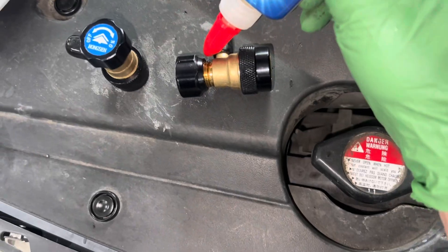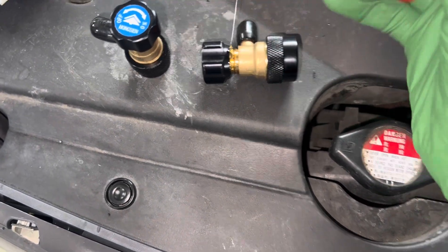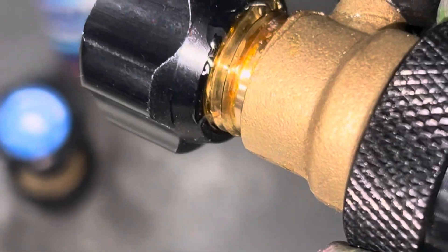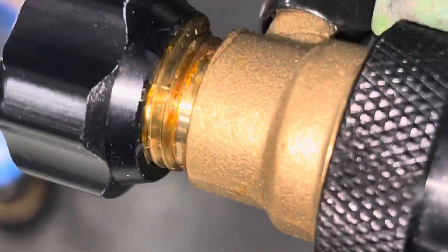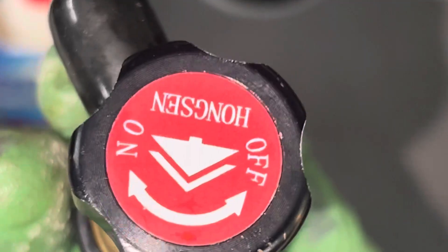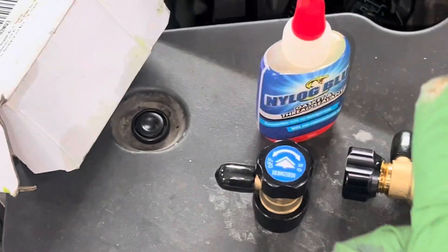I want to go 360 degrees — you see how I did right there, I went on the threads right there. If that goes 360 degrees all the way around, vacuum cannot be pulled up through the center shaft or up through there under that sticker. Those are all potential failure points in the future when it does start to fail. See you guys later.